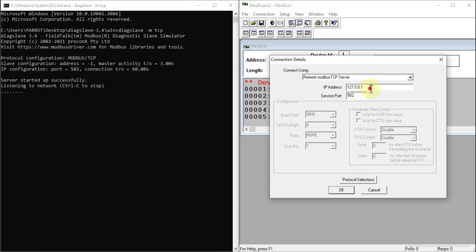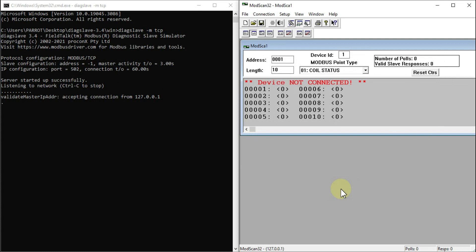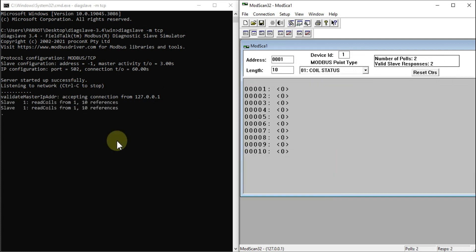In ModScan32, we will go to Connection and click Connect. Here is the IP address of my local system which is 127.0.0.1 and the service port is 502. You can see port number 502 here. We will press OK.